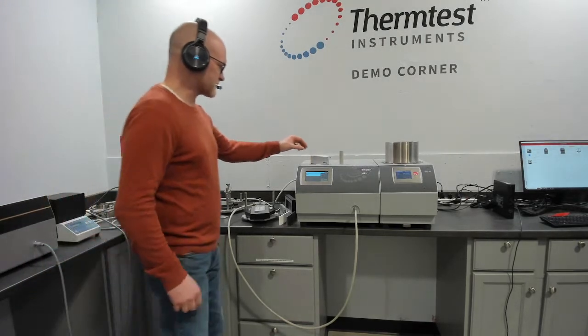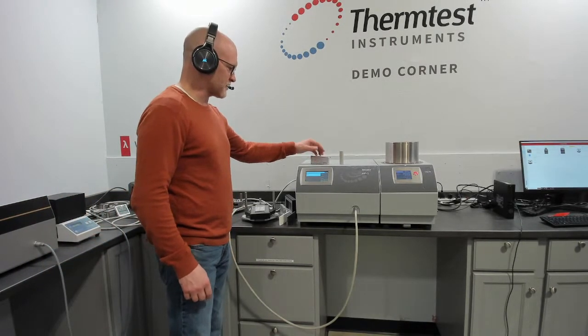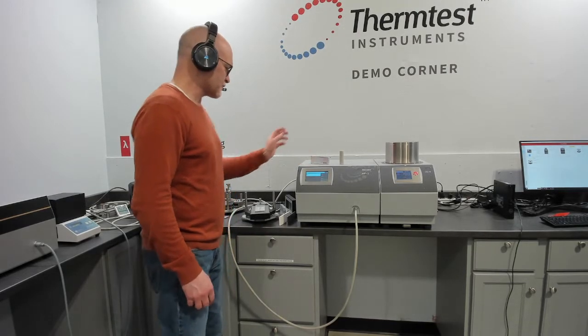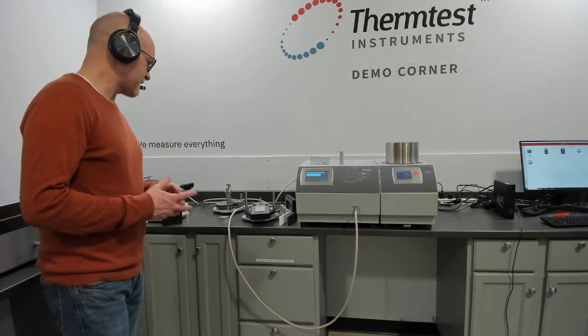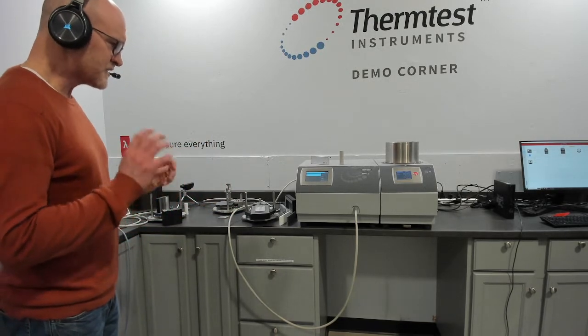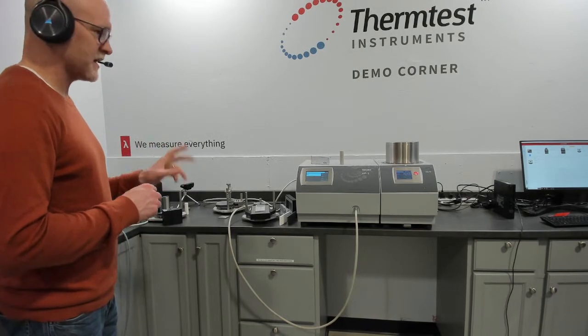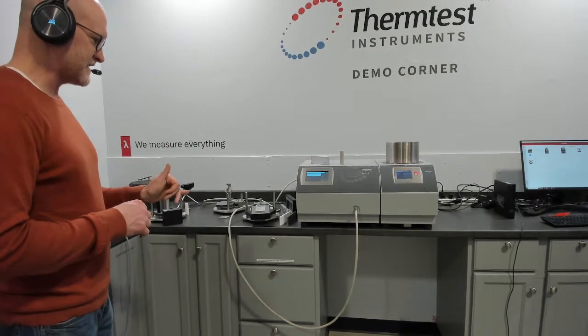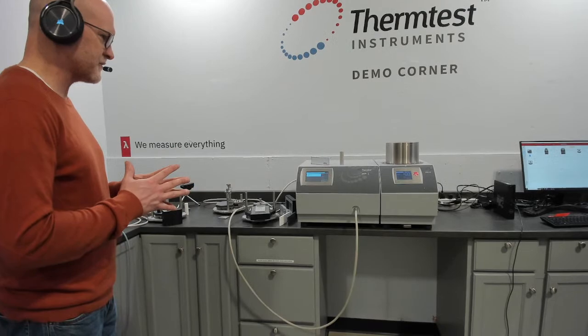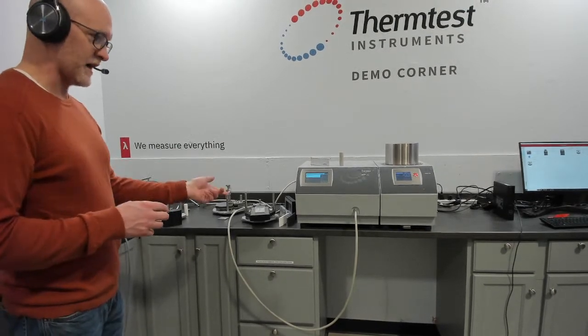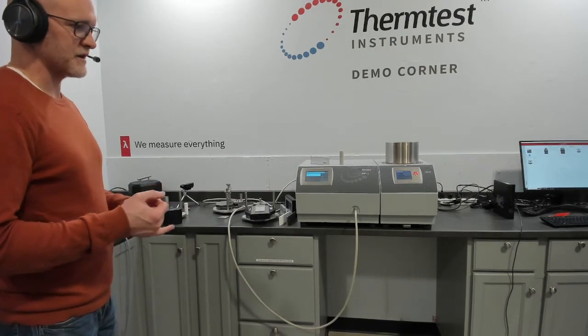But what we're going to talk about today is if your application is the measurement of thermophysical properties of batteries. So we have a battery package that, depending on your battery type, or if you have both of them, we offer 2 types of specific heat sensors.